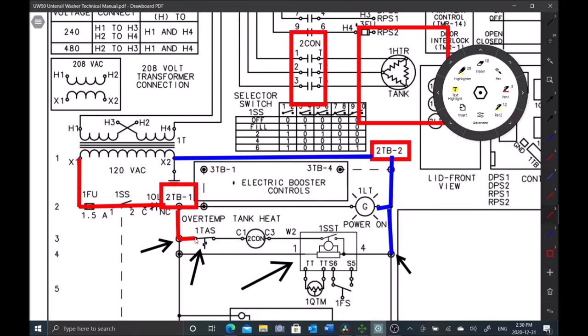Next I'm going to test out this high limit. It's just a manual reset. So it is clicking in. It was tripped. As you can see there this high limit was tripped. That's why we were losing power right here. This was tripped, it was in the open position. Now it's closed and we can complete our circuit.